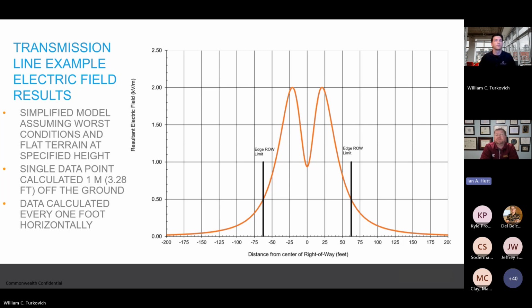In this particular example, we're seeing that our limits are at 1 kilovolt per meter. And we can see based on this analysis, for electric field, that we're below that limit - we're coming in at about 0.5 kilovolts per meter. So we're below the limit for our edge-of-right-of-way values. You can also see for this example that we're at about 2 kilovolts per meter for our peaks.